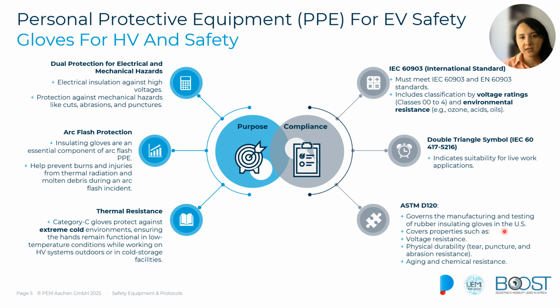And finally, in the United States, we have the ASTM D120. This standard governs how the rubber insulating gloves are going to be manufactured and how they have to be tested. So with this standard, we cover the voltage resistance, the physical durability, and the aging of the gloves. And when we are meeting these standards, it means that the gloves provide a very high assurance of safety in many demanding electrical and mechanical environments.